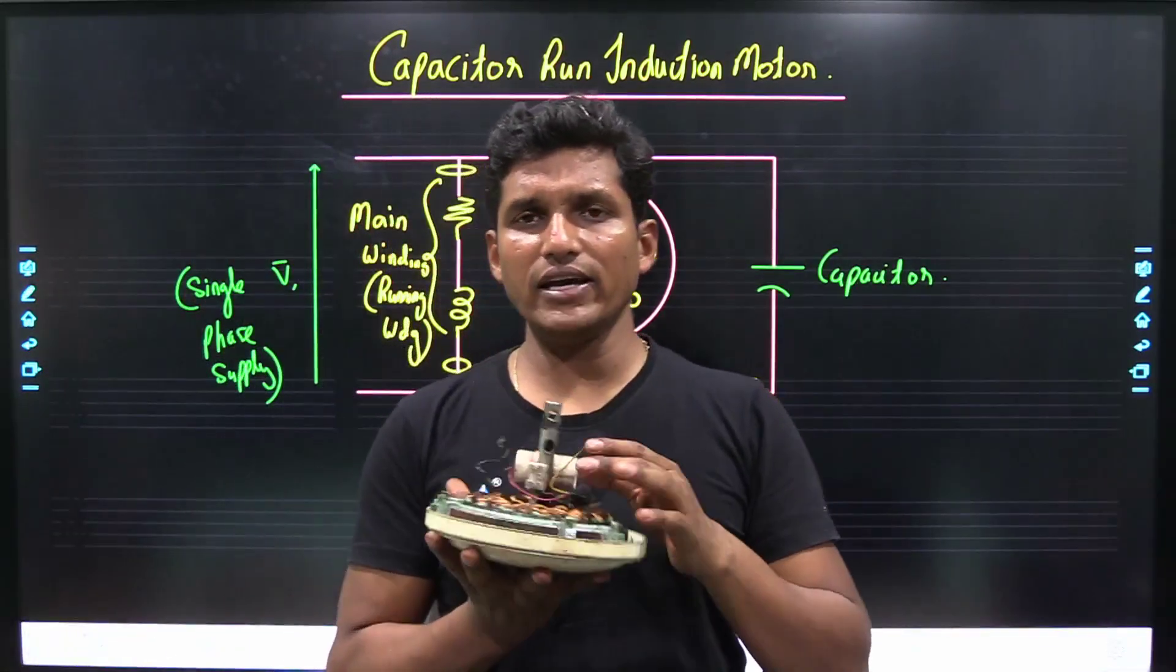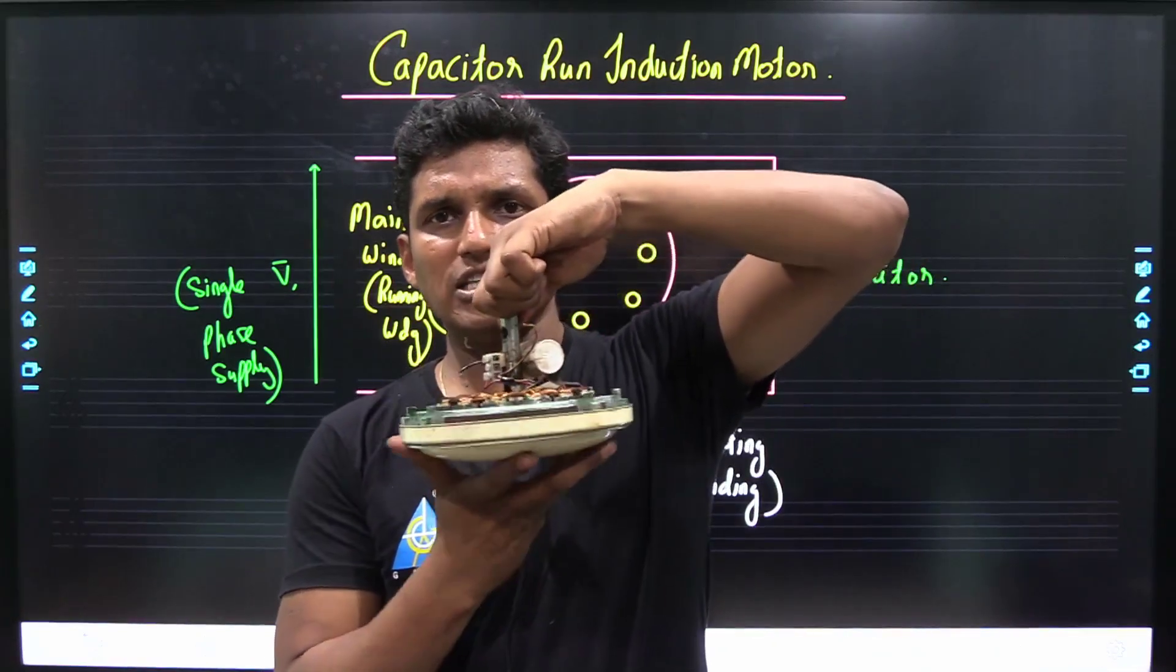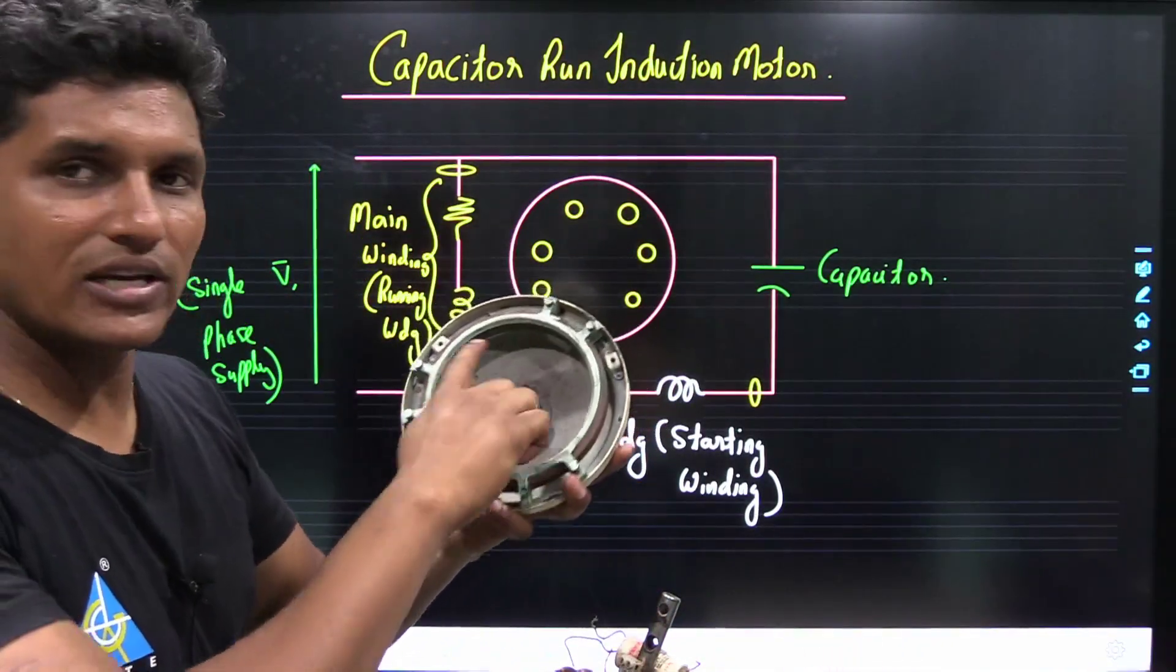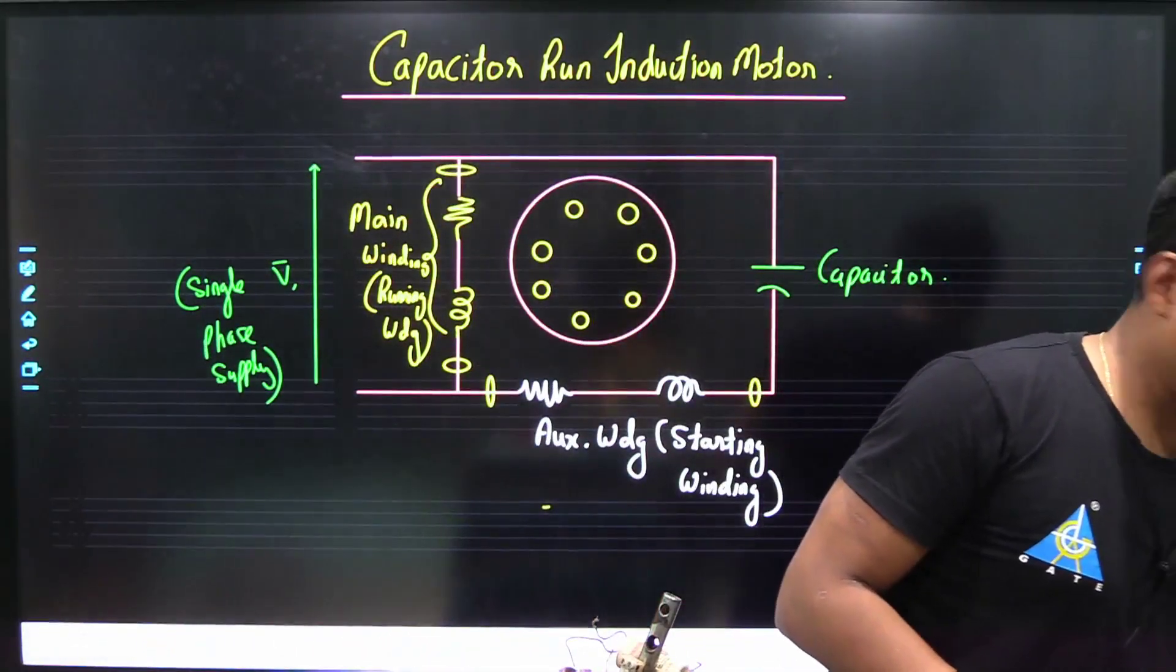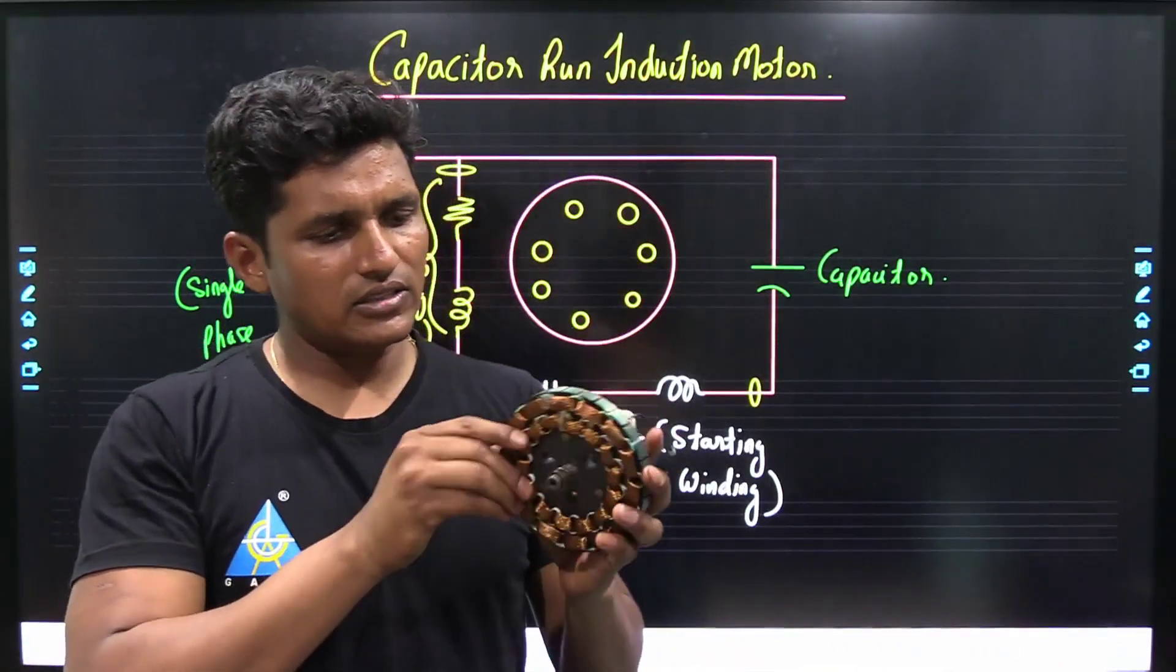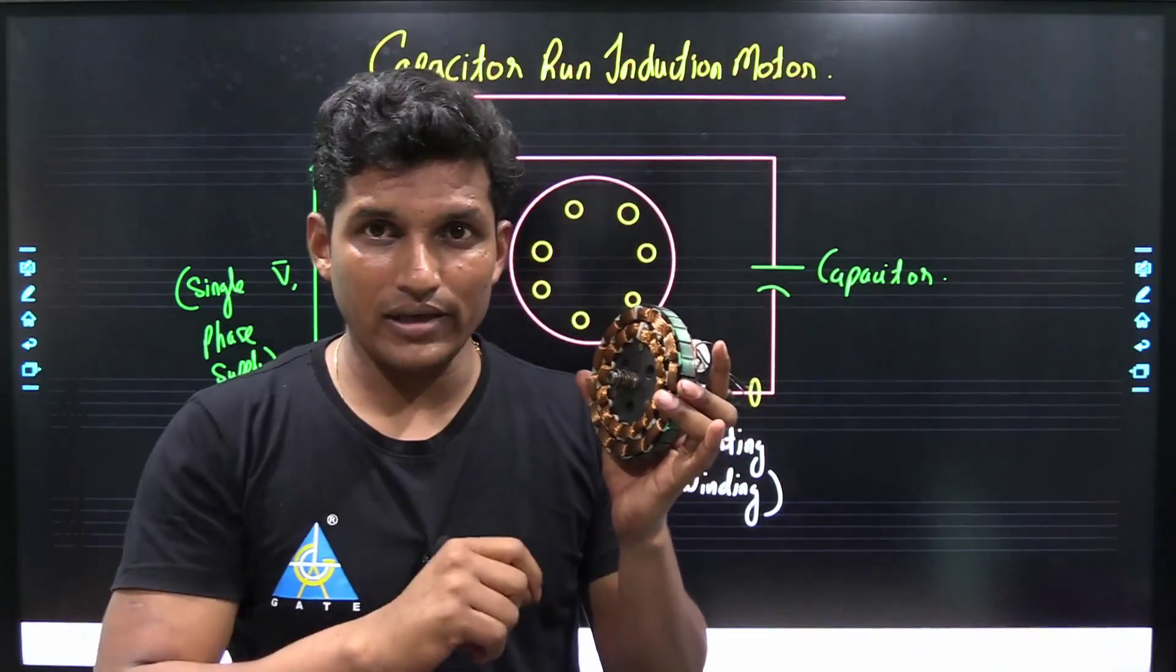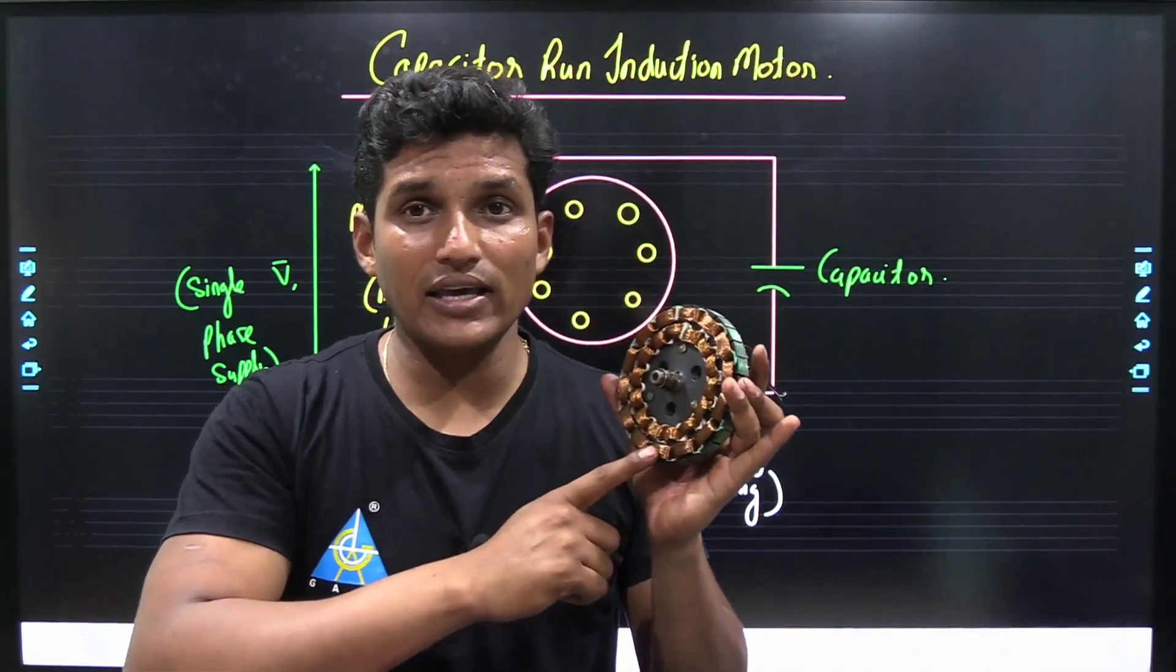Here we are having a ceiling fan in which this is the stator and this one is rotor of capacitor run induction motor. Now, this is the stator of this particular motor in which there are two windings. In the inner circle, that is the running winding or main winding, whereas in the outer periphery, that is where the starting winding is placed.